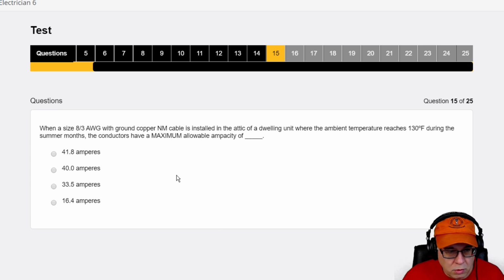It says, where a size 8/3 AWG with ground copper NM cable is installed in an attic of a dwelling unit where the ambient temperature exceeds 130 degrees Fahrenheit during the summer months, the conductors have a maximum allowable ampacity of. Now, this is an interesting question, because I guarantee you that people that run NMB and SE cables in attics do not think about how hot it gets in those attics. It's a pretty good question, but most people don't think about this. But if it's on an exam, you're supposed to think about it.